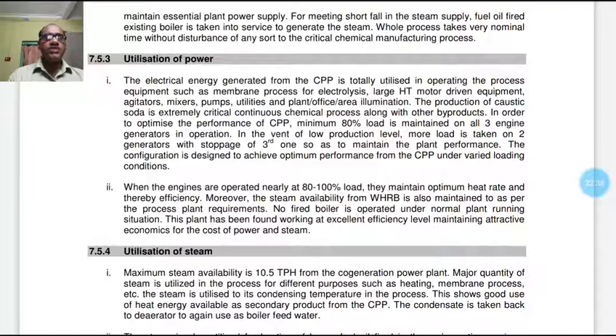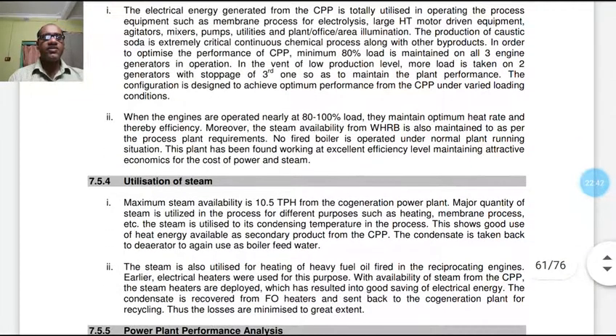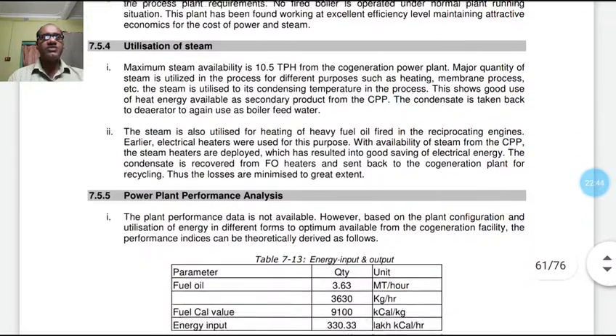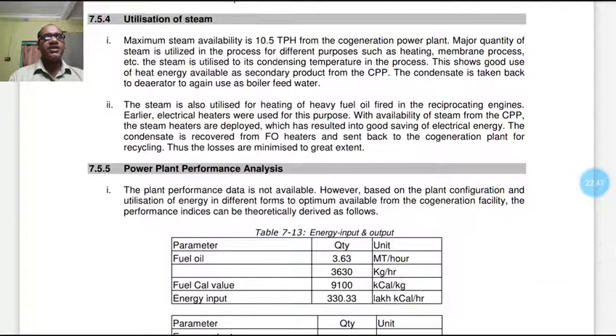Now the utilization of steam: maximum steam available is 10.5 TPH from the cogeneration power plant. Major quantity of steam is utilized in the process for different purposes such as heating, membrane process, etc. The steam is utilized to its condensing temperature in the processes. This shows good use of heat energy available as secondary product of the CPP. The condensate is taken back to the deaerator to again use as boiler feed water.